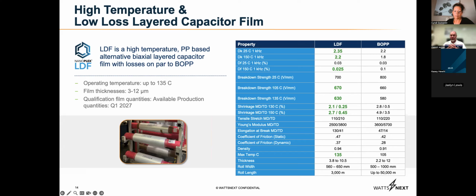The other thing that we see here for our film is that our breakdown strength at elevated temperatures is actually higher than BOPP, and this allows us to design capacitors that don't need the same level of derating that you would get with a polypropylene-based capacitor. Next slide.